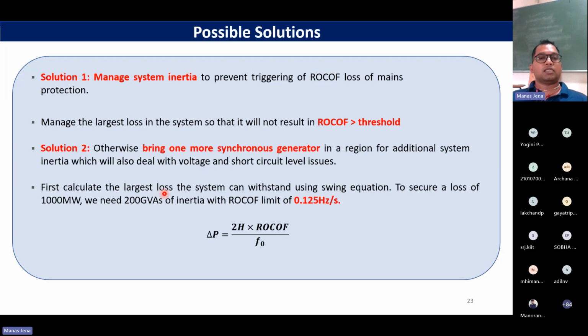So first, calculate the largest loss the system can withstand using the swing equation. Say, to secure a loss of 1000 megawatt, and this 1000 megawatt may be 4000 megawatt for our grid, we need 200 GVA·s of inertia and a RoCoF limit of 0.125 hertz per second. This RoCoF limit varies from operator to operator. So essentially we need to look at the maximum inverter penetration from the perspective of maximum RoCoF, or the maximum loss that I can withstand which will not breach this RoCoF threshold.